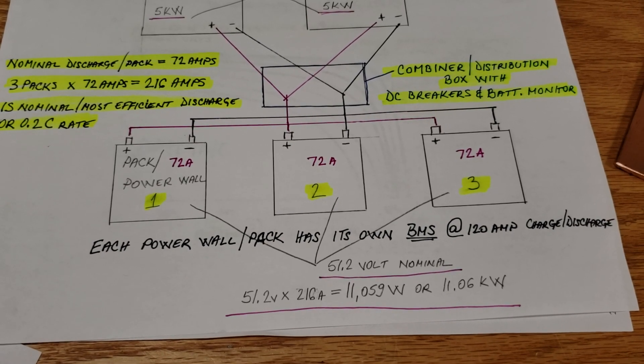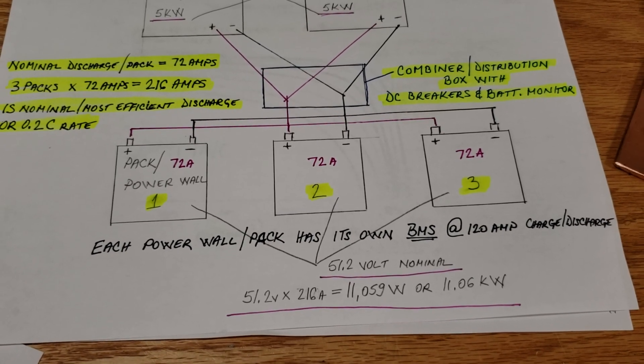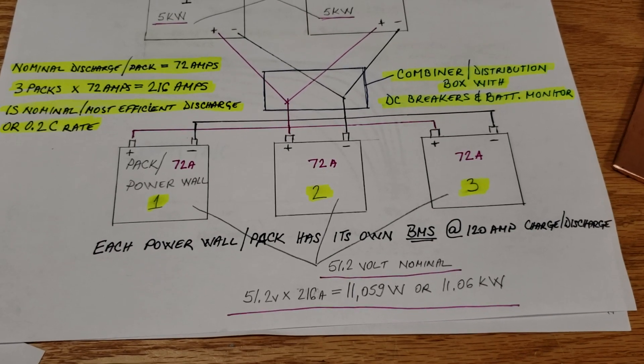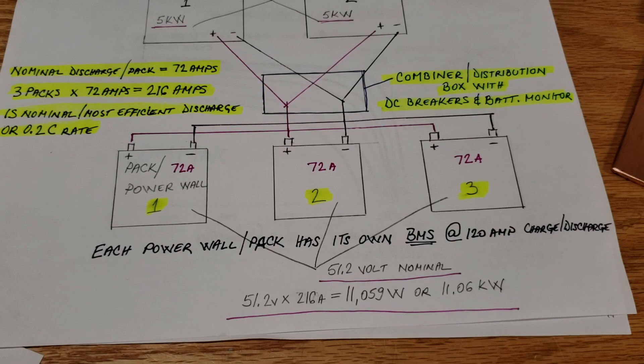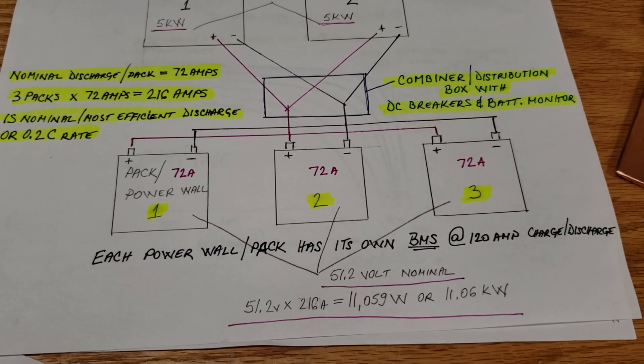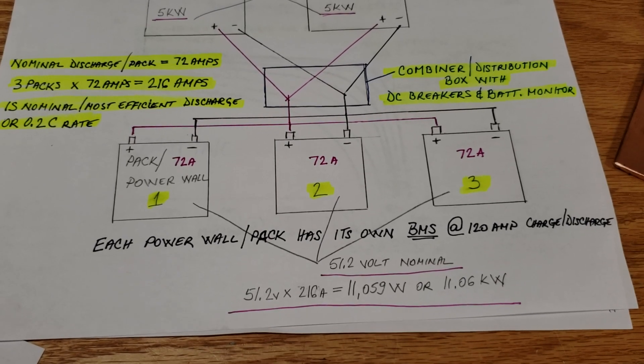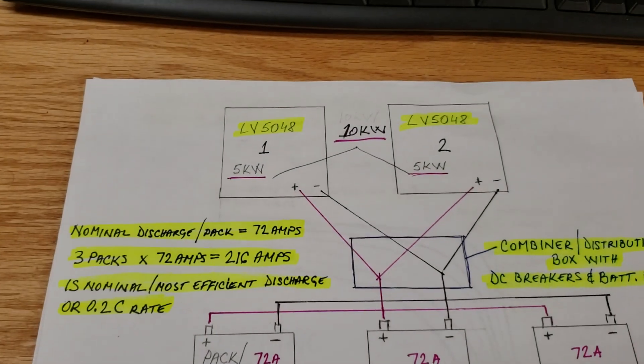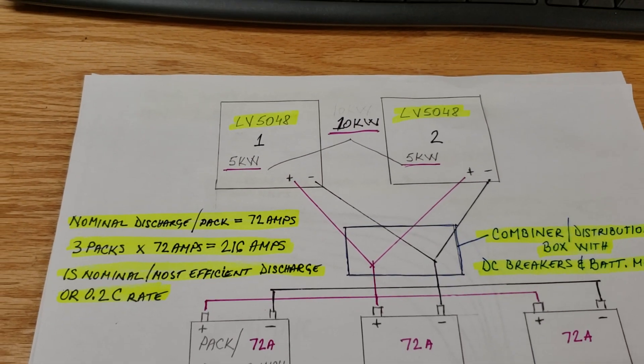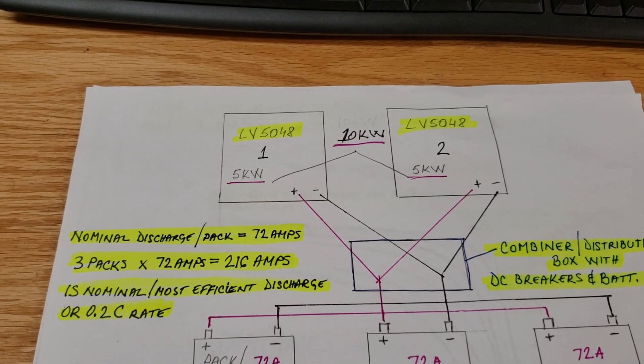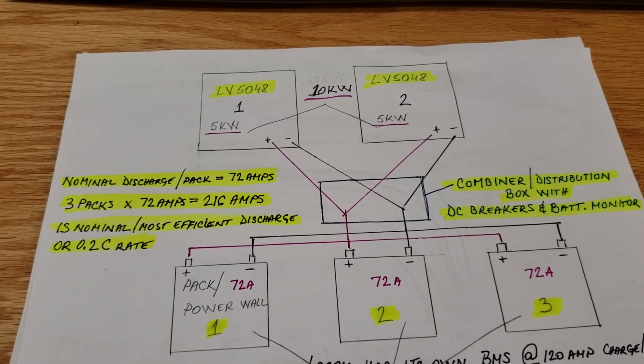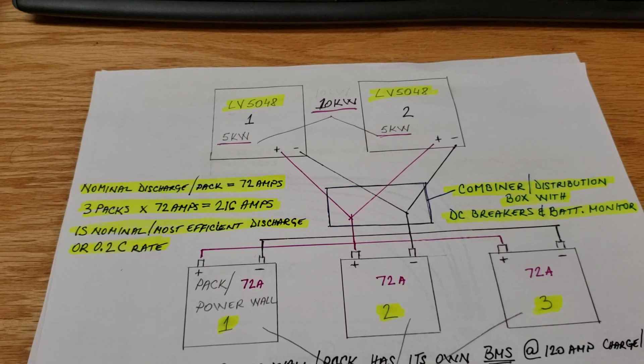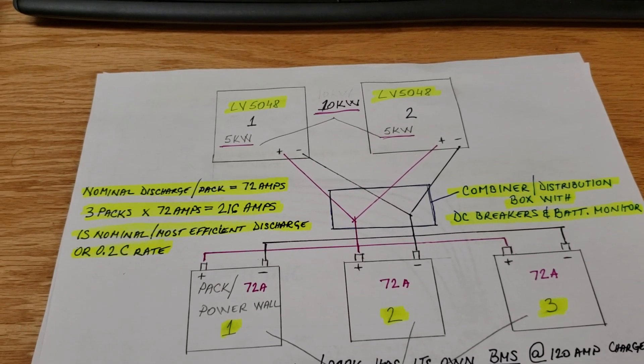I think this will work very well for me and my system. This will provide longevity, this will provide minimum heating up during the charging and discharging cycle of the batteries. I will probably never use it at 216 amps at the same time because 11.06 kilowatts is a whole lot more than 10 kilowatts. Yes, there is some exchange rate between the efficiency and the batteries. This is about the max that I can use, and that max of two LV5048s, I'm still at 0.2C rate discharge for my battery system or power wall system.